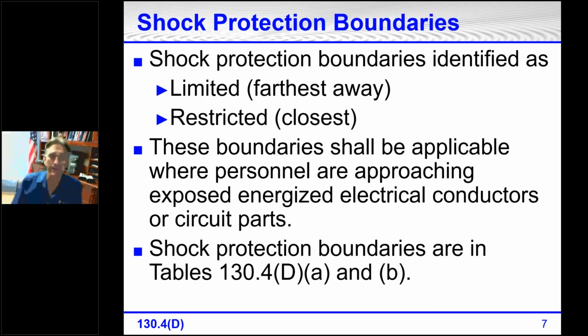All right, the shock protection boundaries. I mentioned this. We have two. The limited is the furthest away. The restricted is the closest. We used to have a third boundary, two or three editions back, that was called the prohibited approach boundary. That boundary was eliminated because you had to do nothing different when you were about to cross the prohibited approach boundary than what you already had in place for crossing the restricted approach boundary.